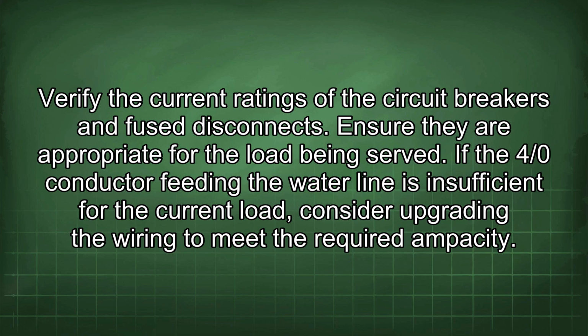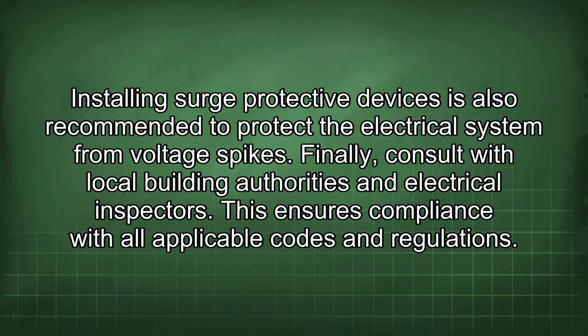If the 4/0 conductor feeding the water line is insufficient for the current load, consider upgrading the wiring to meet the required ampacity. Installing surge protective devices is also recommended to protect the electrical system from voltage spikes. Finally, consult with local building authorities and electrical inspectors. This ensures compliance with all applicable codes and regulations.